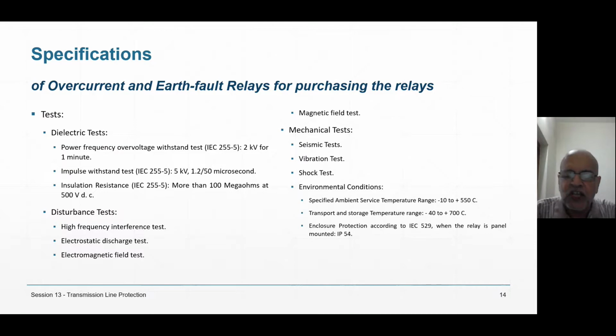Shock test. Shock test means the relay is kept, and a 100-gram hammer is kept vertical, and then from vertical it is dropped and it will strike the relay. The relay should not be damaged. That shock test I have done for meters. You see, all these tests, if you see them yourself, then you will be master of things.